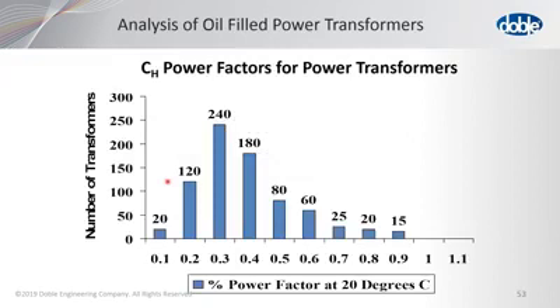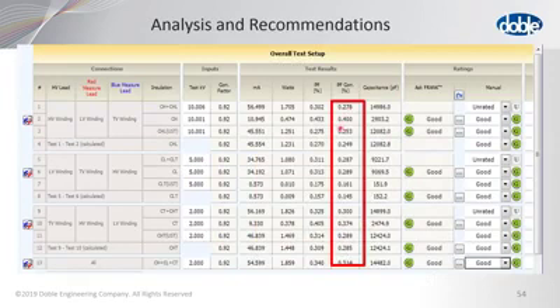Okay, now how do we analyze the results? Here we've got some nice numbers and everything, and we want to say, what's the value of these? Well, we do what we call tabulations of many, many test results. Now, this is just a small sampling. We've got thousands and thousands or more in our DTA web. But in this particular sampling, 240 of the tests for CH had power factors in the 0.3 range, and 180 were around 0.4. This is how we identify the locations where we're going to put the limits. And notice in this particular case, all these power factors are below 0.5, and we've given them a G rating.